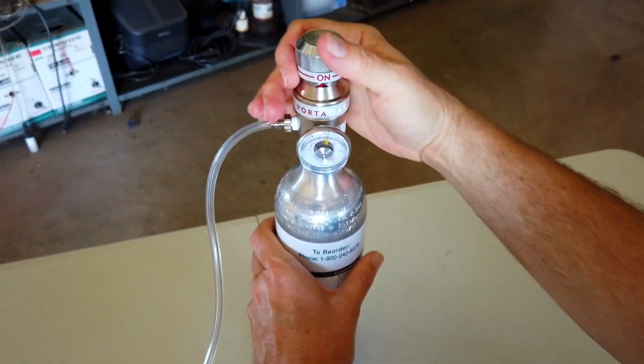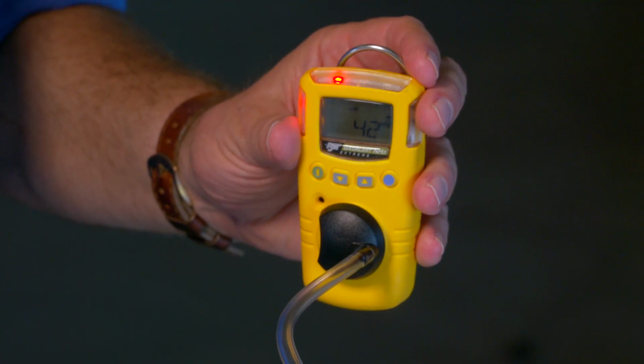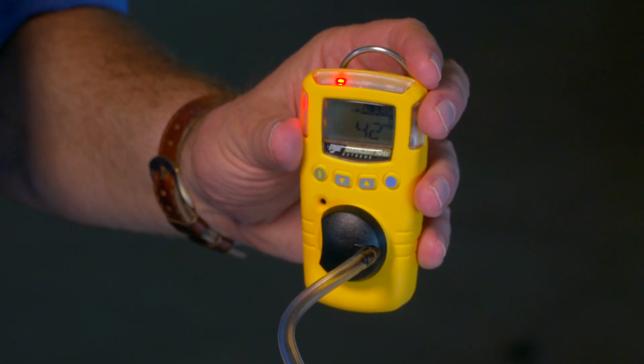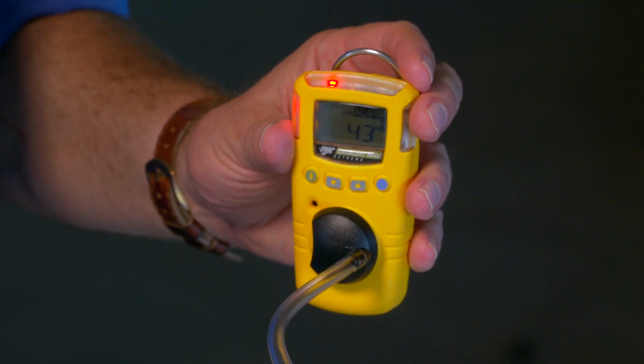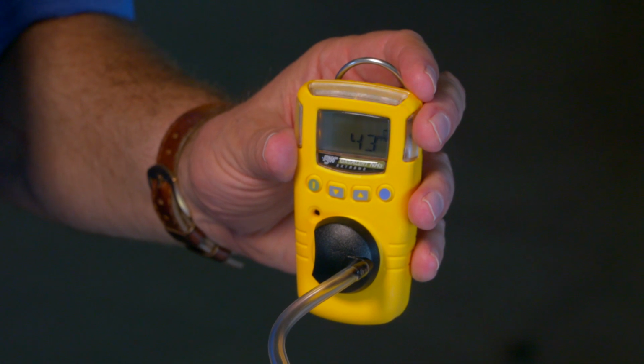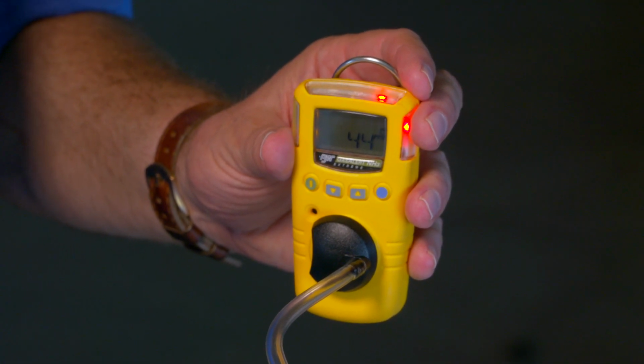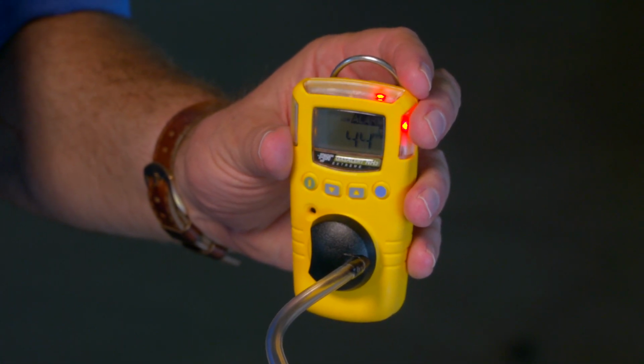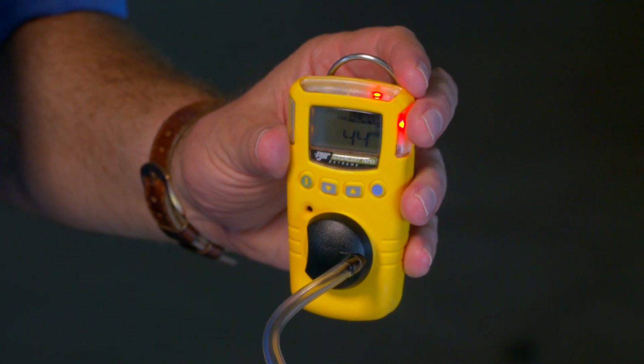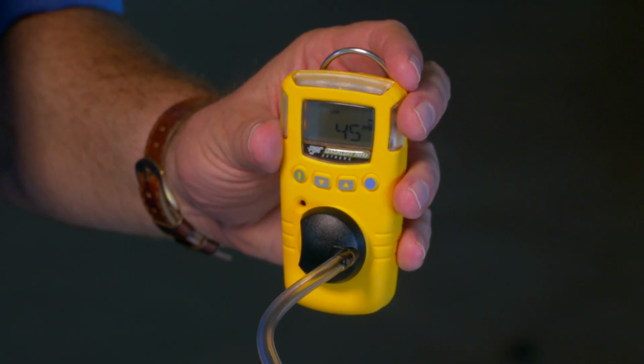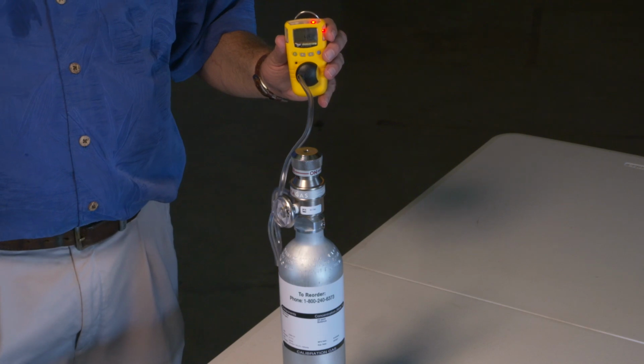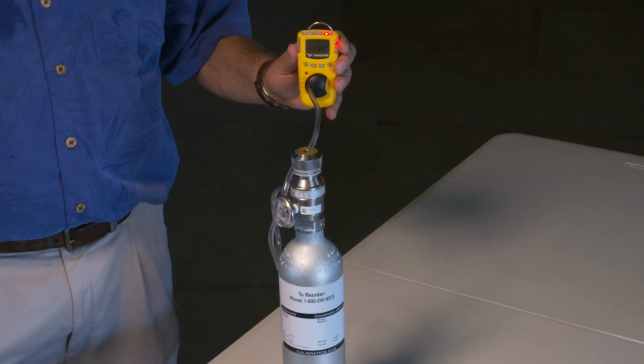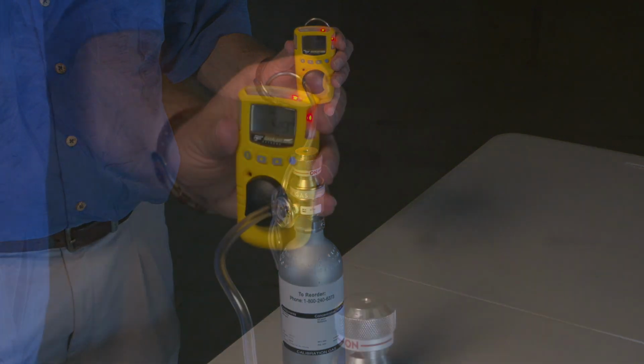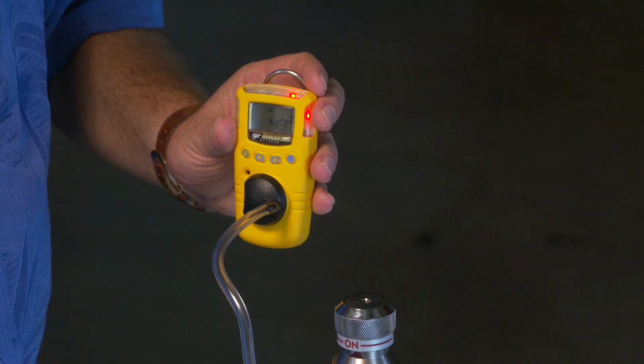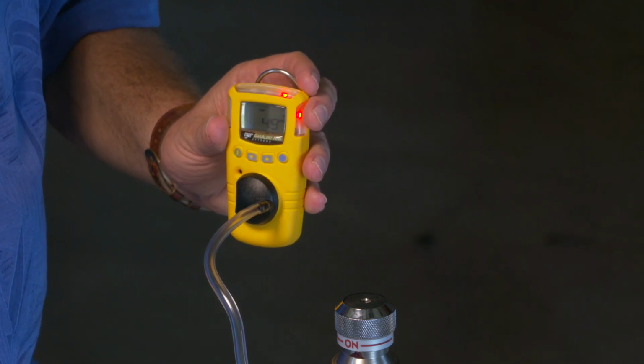The second test that you're going to want to perform is called a bump test. The purpose of a bump test is to check the sensors and to be sure that they are working properly. It is not a test of accuracy. Bump tests should be done on a daily basis or after any alarming event. It uses just a whiff of those known test gases to run across the sensors and to be sure that they are all functioning properly.